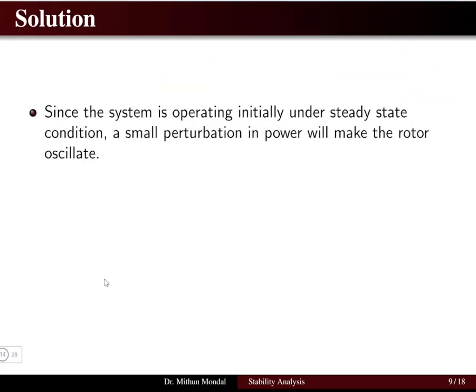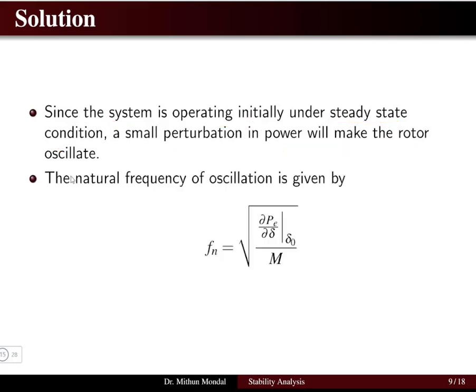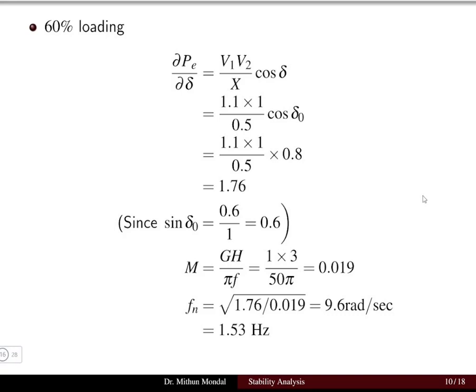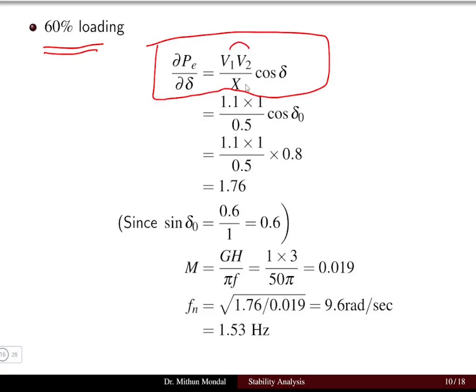When the system operates under steady-state and a small perturbation occurs, the rotor will oscillate. The natural frequency of oscillation is given by ωₙ = √(dPe/dδ|δ₀ / M), where M = GH / (πf). The power-angle relationship is Pe = V₁V₂ / X_total × sin δ, so dPe/dδ = V₁V₂ / X_total × cos δ₀.